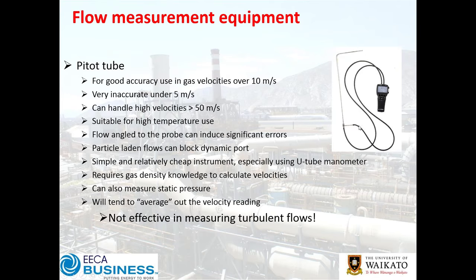A pitot tube is generally good over 10 m/s and increasingly inaccurate under 5 m/s. It's good for high temperatures and high velocities provided your DP cell can handle the pressure. Particle-laden flows can block the dynamic port and give a poor reading. You need to know a lot about gas density for flow calculations. It can also be used to measure static pressure, which is useful. The pitot tube gives a time-averaged flow reading rather than an instantaneous turbulent flow reading.